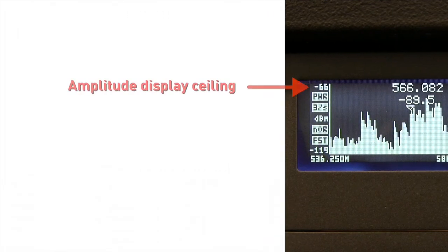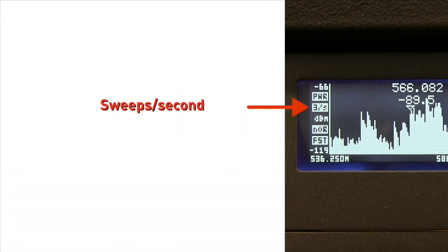The first icon is the highest amplitude displayed. The second is the status of the USB connection. The third, the number of sweeps the RackPRO performs per second. This number is determined by the frequency span, which we'll show you how to set momentarily.